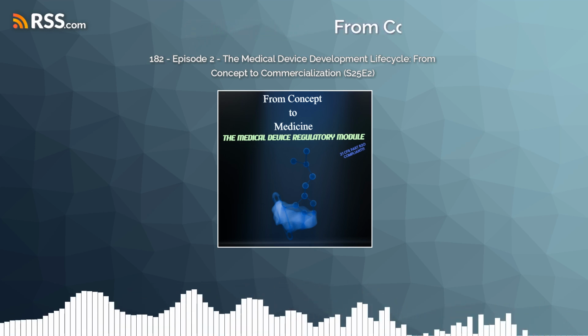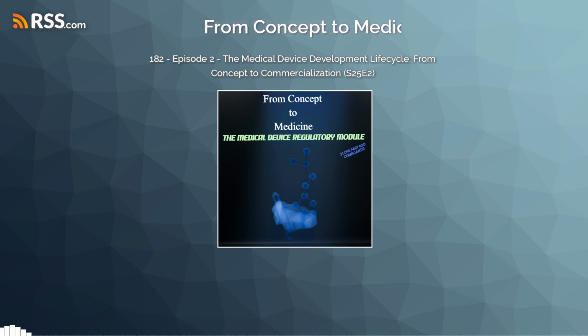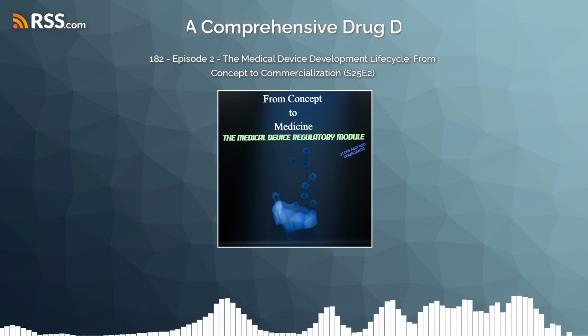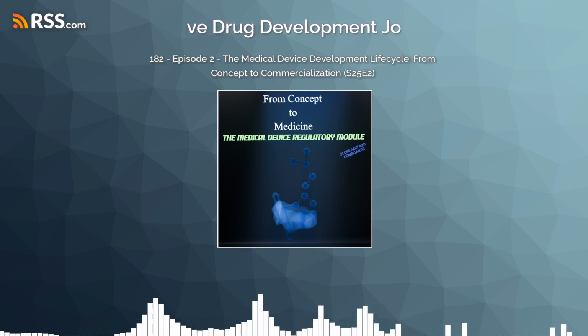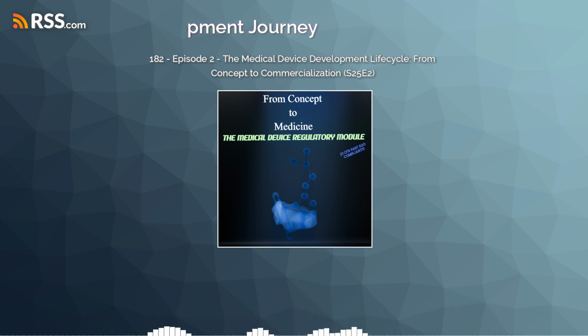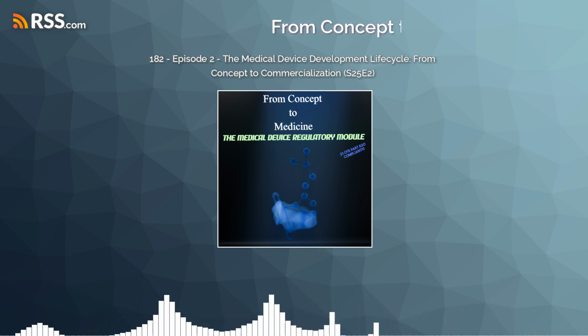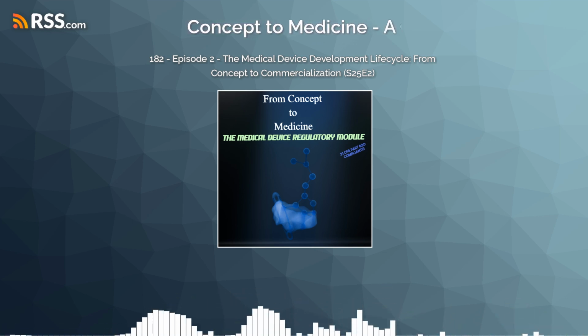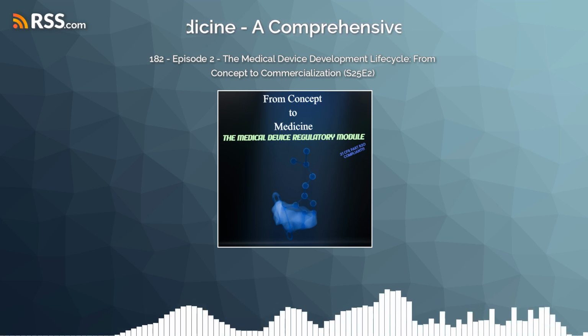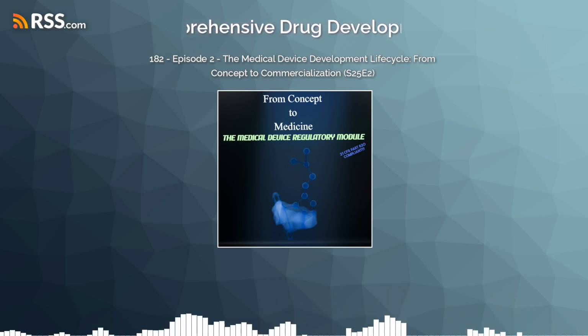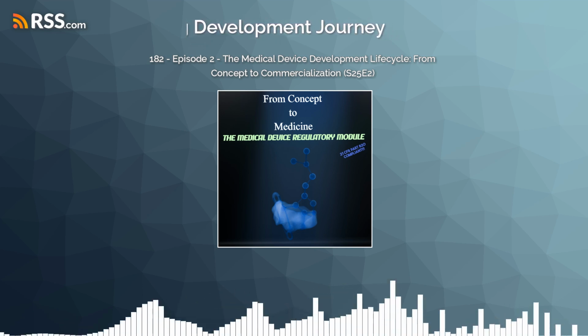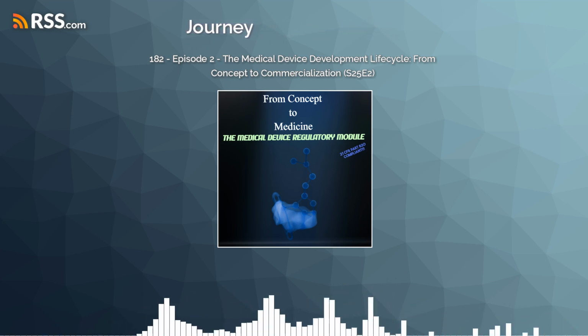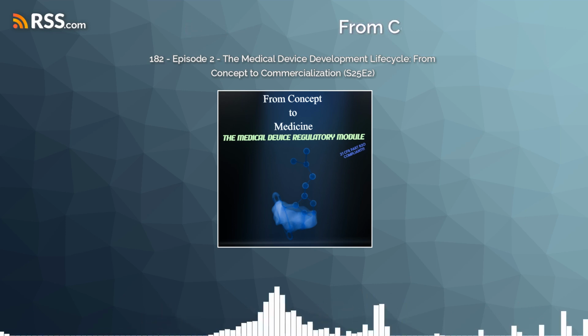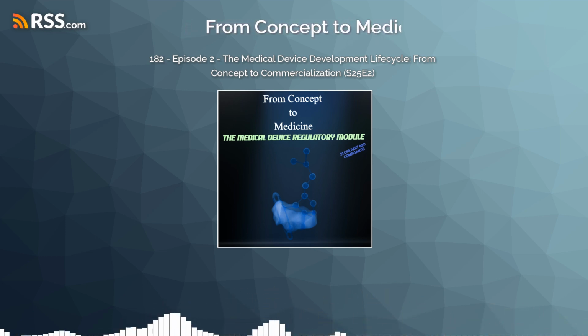So with all this focus on documentation and proving things, what about all the testing that happens during design, before you even get to humans? Yes. That's where non-clinical testing comes in, and it operates under good laboratory practices, or GLP. GLP, right. Heard that one before. Yep, 21 CFR Part 58 in the U.S. GLP isn't just about doing good science. It's about ensuring the data itself is totally reliable, like trustworthy enough to base safety decisions on. So what kind of tests are we talking? Rigorous lab studies, things like analytical tests, sensitivity, linearity, cross-reactivity, precision testing, basically proving the device works reliably and accurately in a controlled setting.